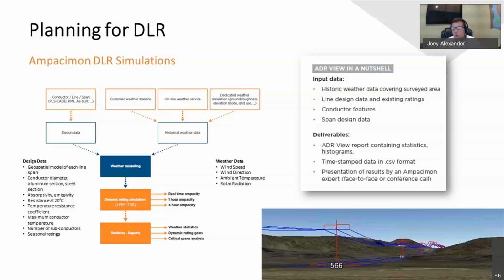That's important because we use that model to input historical weather data, recreating the past of this line to see what the dynamic line ratings would have been had we had sensors on those lines at that point in the past. So we input wind speed, wind direction, ambient temperature, and solar radiation into the model.